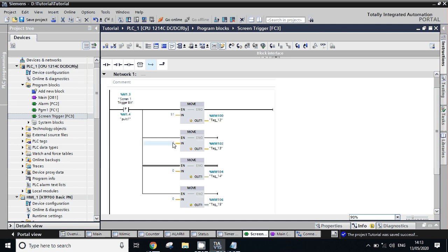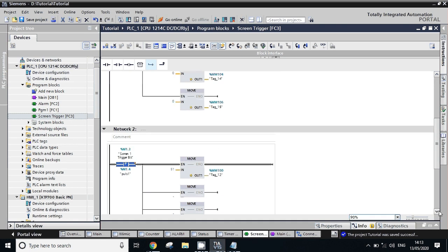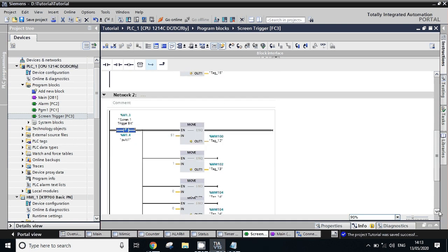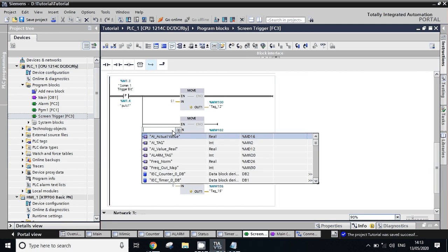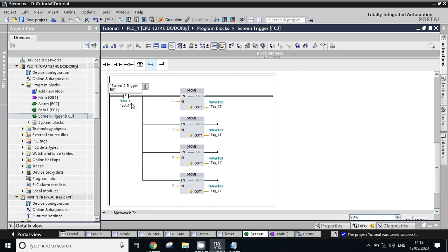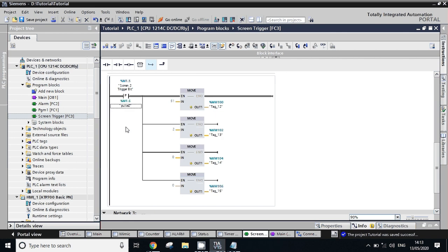We'll take one more ladder for screen number two. Just copy this, paste this. Now this is for two - you have to just change this screen number. Now we will take the second screen and here we will take another bit that is for screen number two. We have to modify this also. So when your M1.5 bit will be triggered, second screen will be appeared.